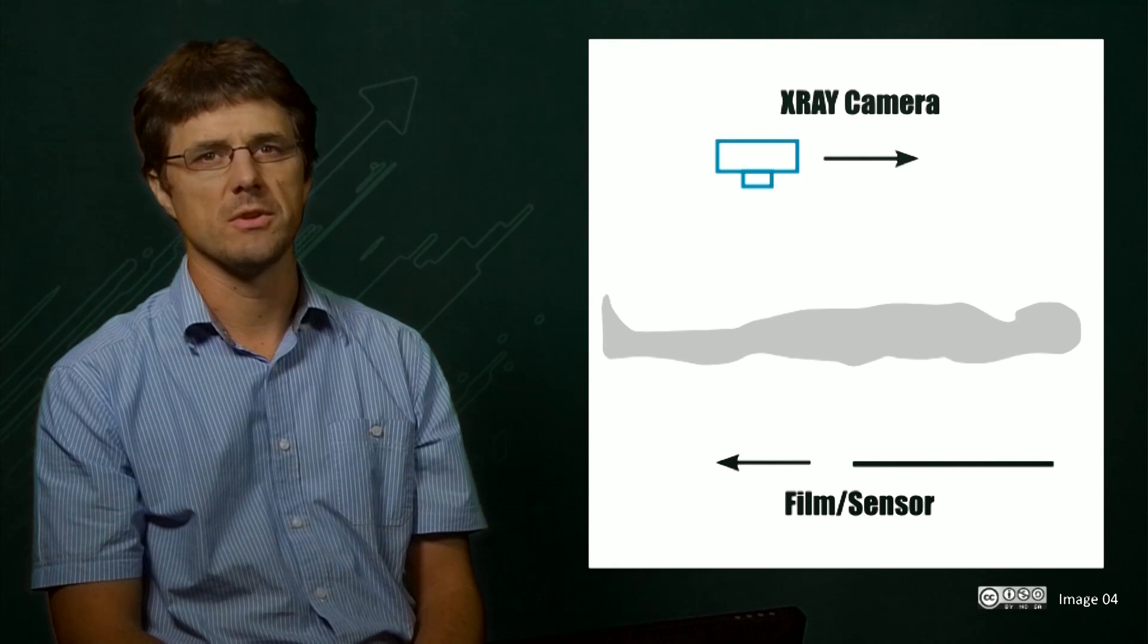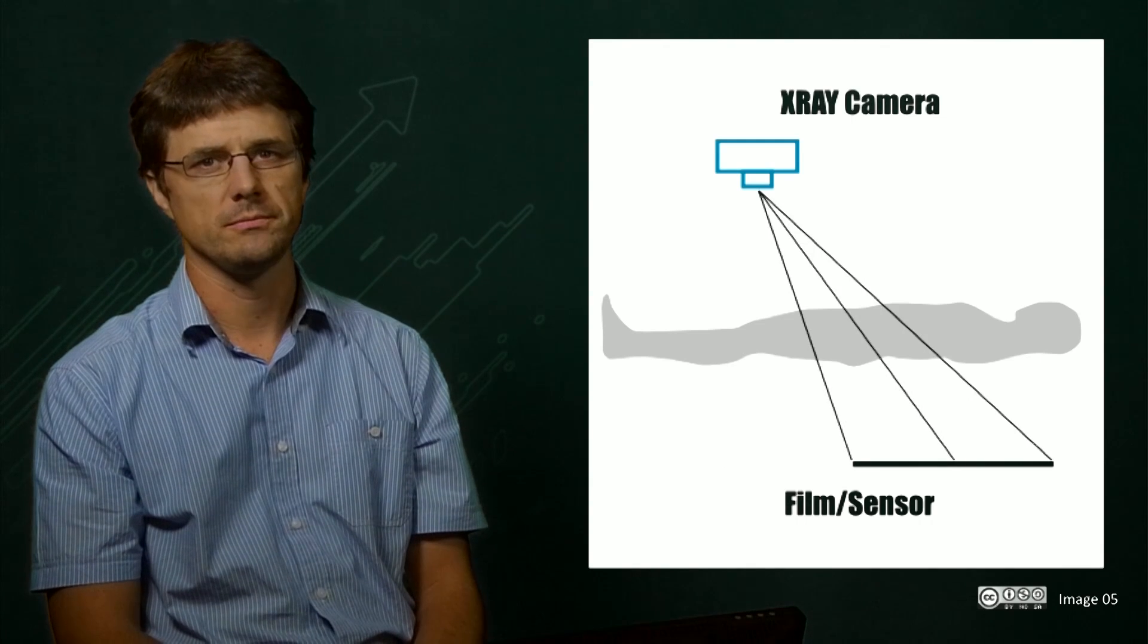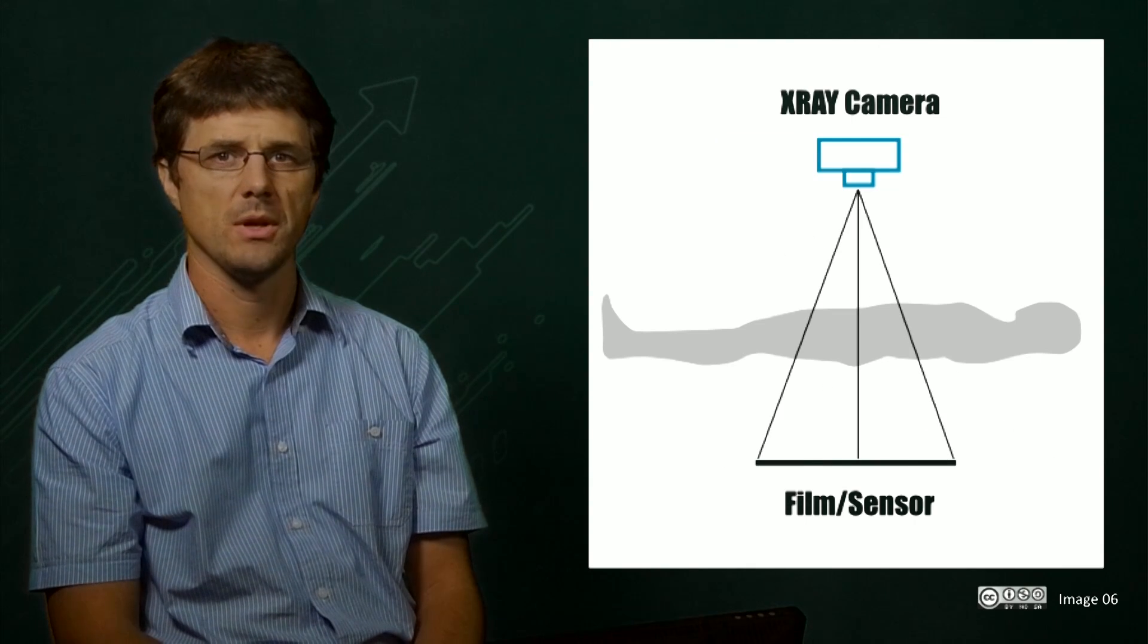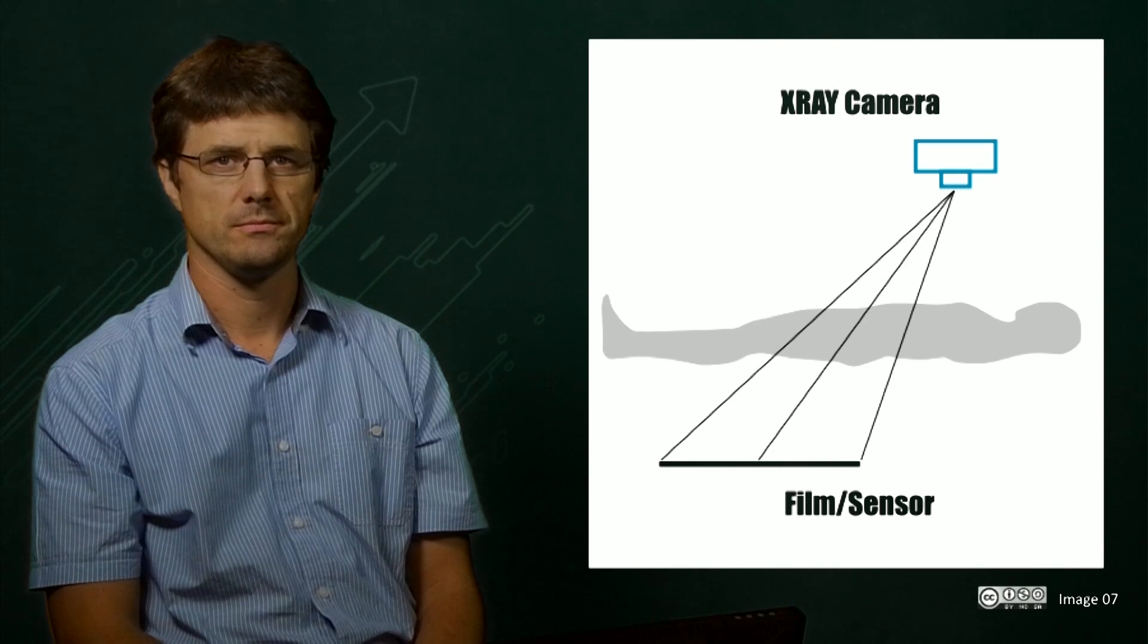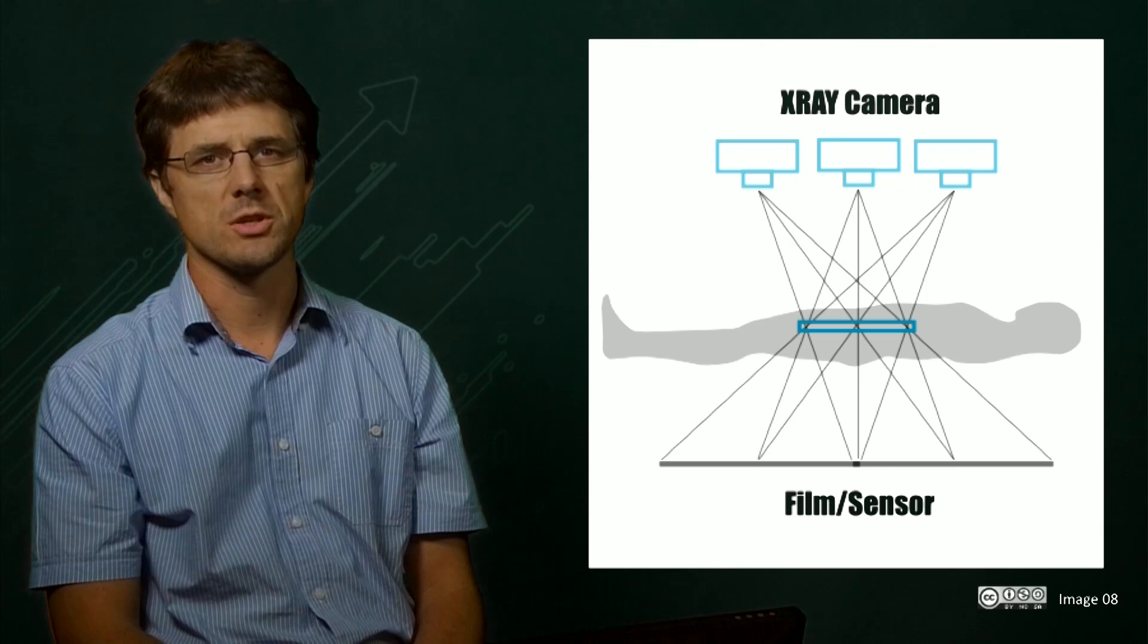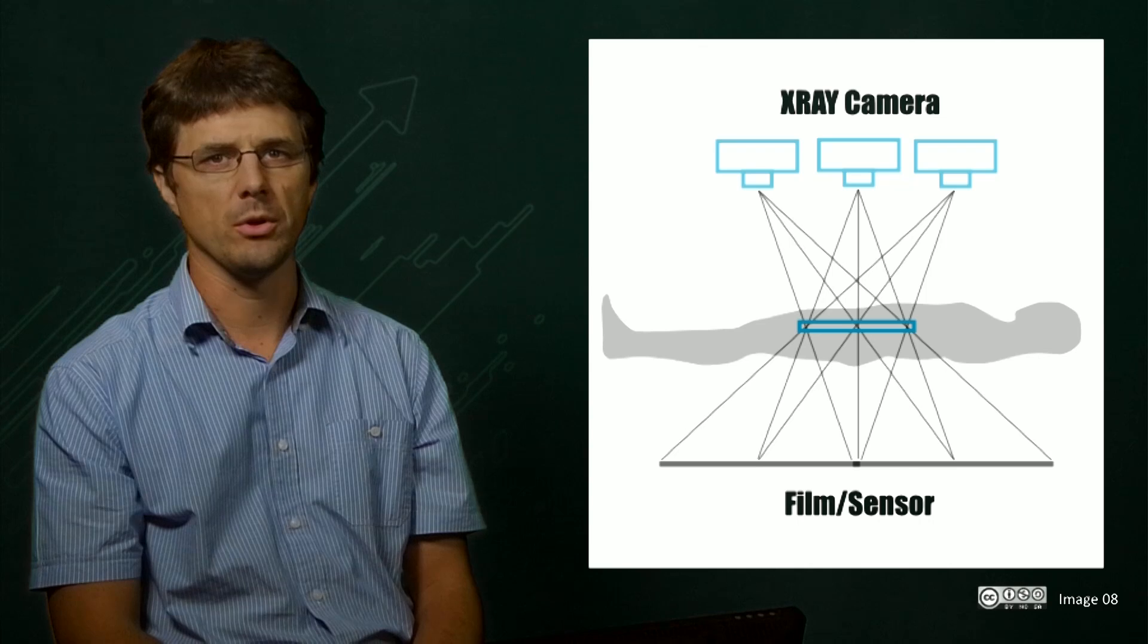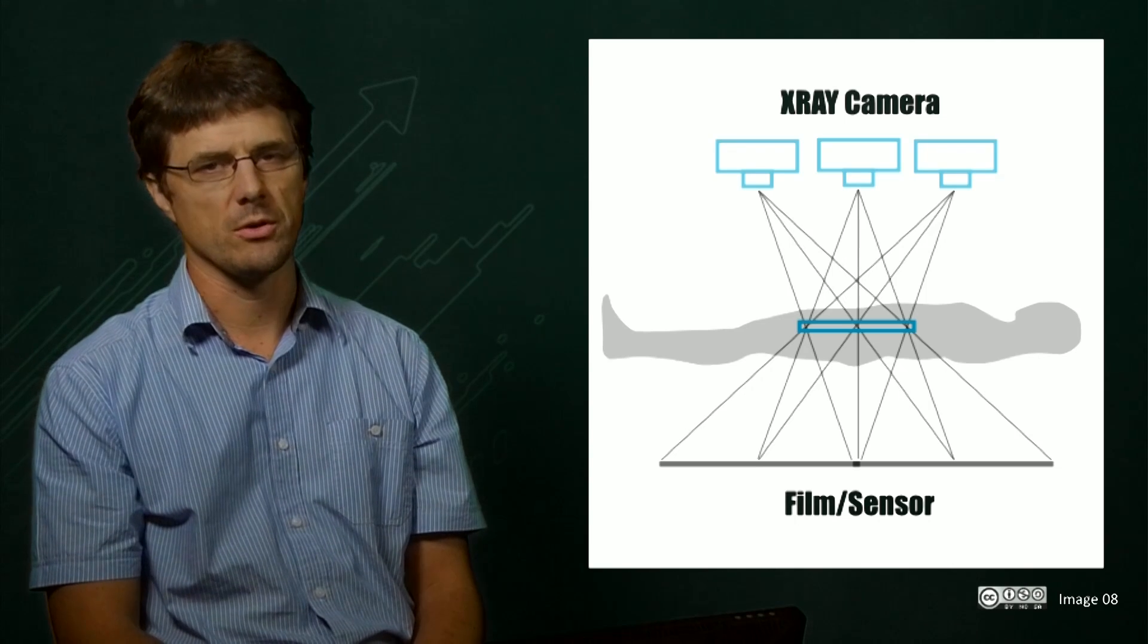We can get a better understanding of this by looking at how the image will be projected at one extreme, the centre, and the other extreme. By moving both the camera and the film, only a single plane will remain in sharp focus, whereas contrasts from above and below this plane will be blurred as its position will not be constant on the film.